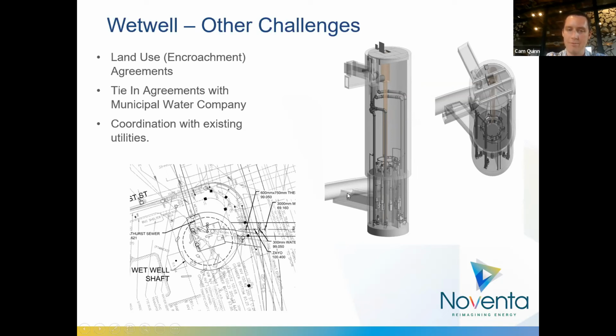We know from Toronto Water that there's material like 2x4s, bicycles, and other unique items, fairly large, that won't go through the screen and will probably make it into our system. So on top of the screens, we have the ability from the surface to raise a basket that would capture any large debris and bring it straight out without entering the wet well. If we need to service the sump pumps, we will need to enter the wet well, and we do have the isolation required to do so while keeping part of it operational. That's something we're looking at on maybe a 2-year time frame, not something we'd want to do monthly.